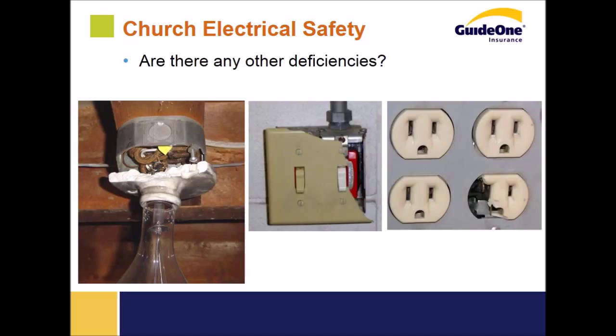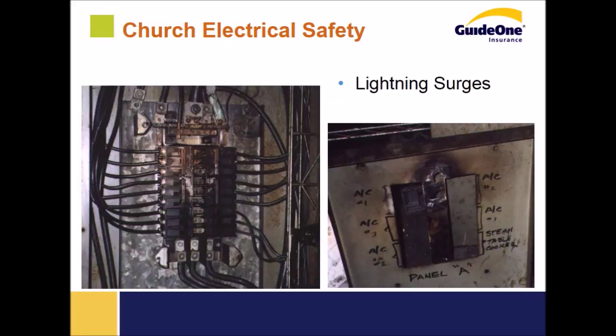Also note and report any damage to lamp holders, covers, or outlets so we can address the concerns. We have electrocution potential here, and also the potential for entry of dust, dirt, and debris that could lead to arc flashing and degradation of this equipment.